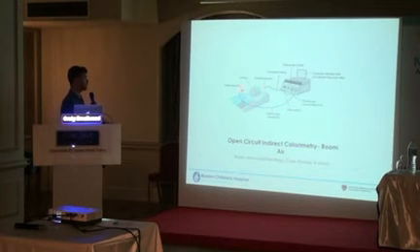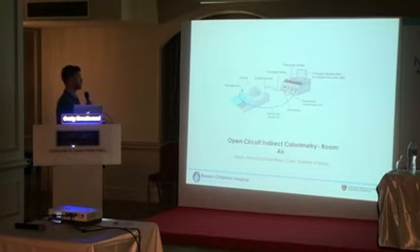So you put this over, there's actually a drape that hangs down here trying to make as much of an airtight seal as possible. And right here, there's a little port. We're going to measure the fresh gas concentration, so that's essentially the partial pressure of oxygen, as well as CO2 just in case there's some in there, but if there is, we're in trouble. And then the patient breathes in, exhales, and through this exhalation port, it's aspirated back into the device by a specific sample flow rate, and then measures the concentrations of gas there as well. And so what you can do is get a non-invasive metric of energy expenditure with a canopy setup IC device.